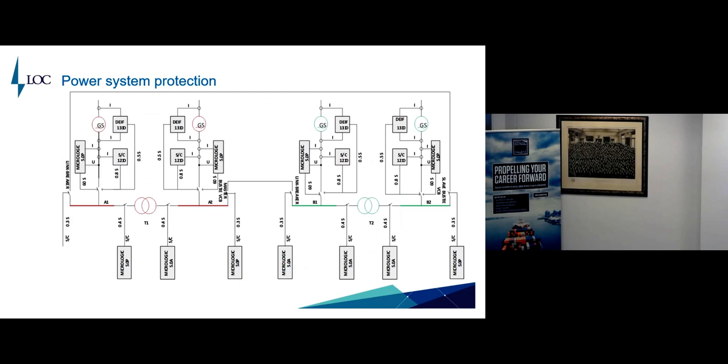You see that this is the same thing, how the system is protected. You can see from here all this relay logic. So now this can be operated as a ring system. If you close this bus tie, then everything will work as a ring system. If there is a short circuit here, you can see there is 0.3 seconds, within 0.3 seconds the bus tie breaker will open. For example, if there is a short circuit here, this will be isolated, and this healthy section will maintain the position, giving power to the thrusters and holding the position of the vessel.